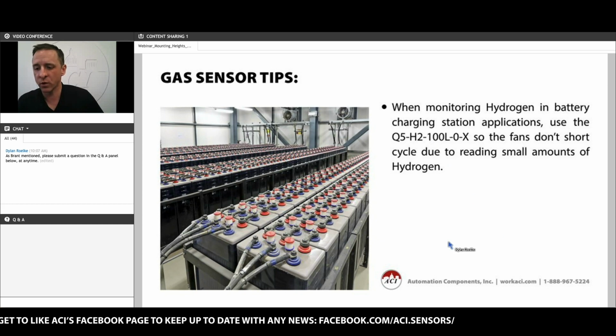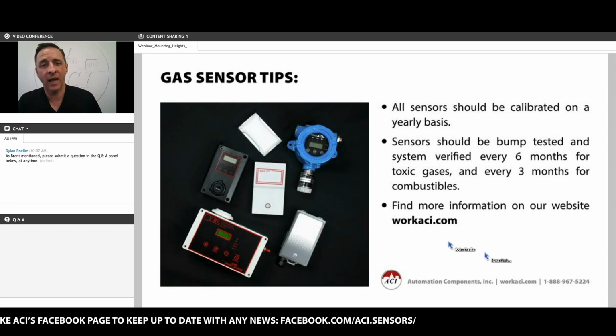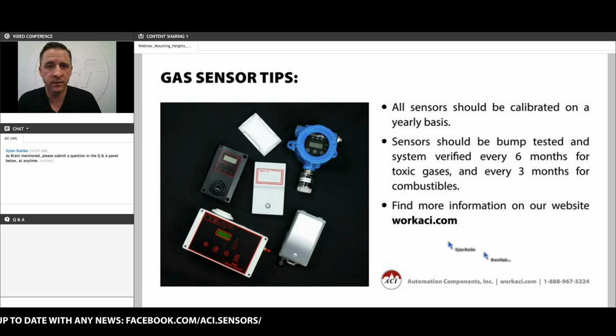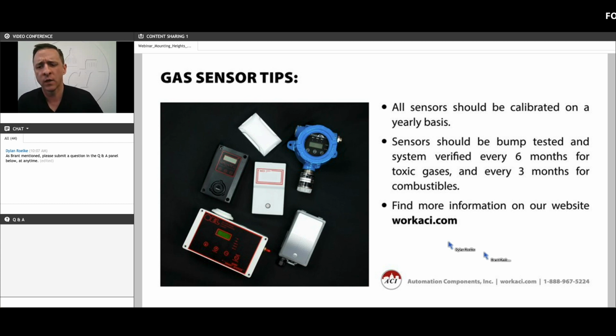Lastly, today, we're going to talk about the calibration intervals for these sensors. All of our toxic and combustible gas sensors should be calibrated on a yearly basis, and that's again in the absence of any specific job requirements or building codes that would require more frequent calibration. These sensors should be bump tested to verify their functionality and accuracy about every 6 months for toxic gases and about every 3 months for combustible gases.